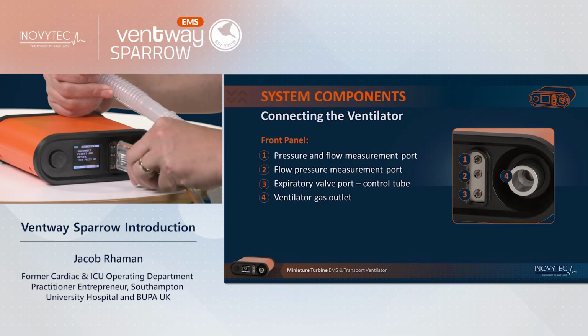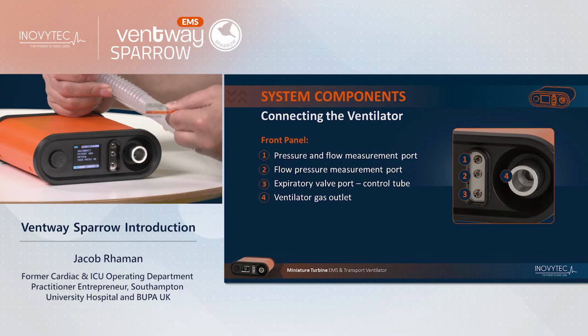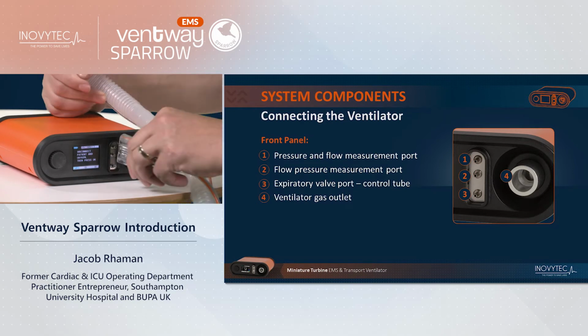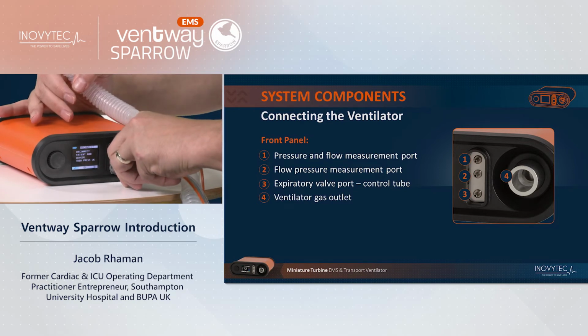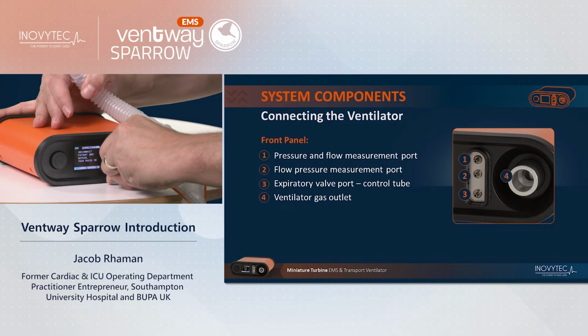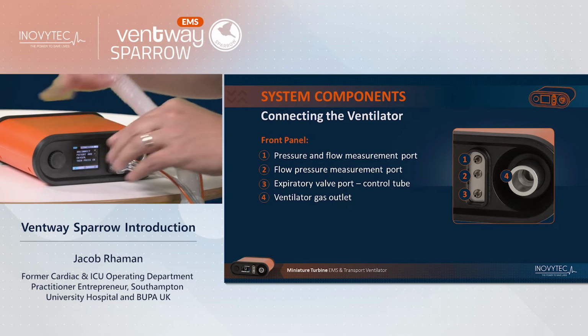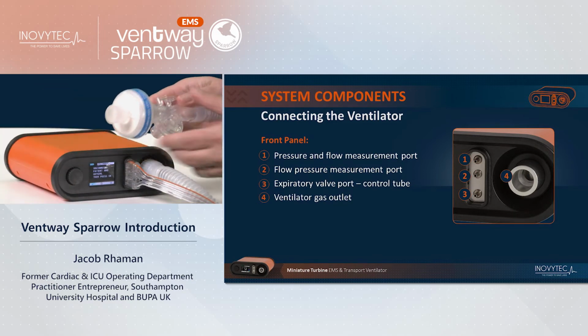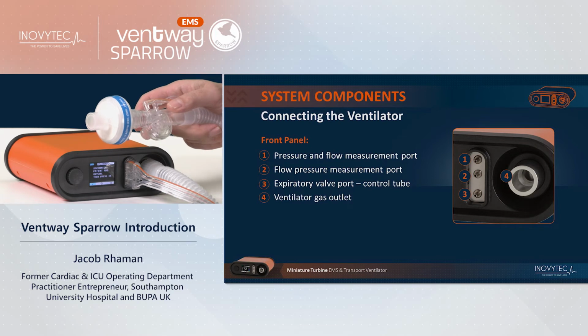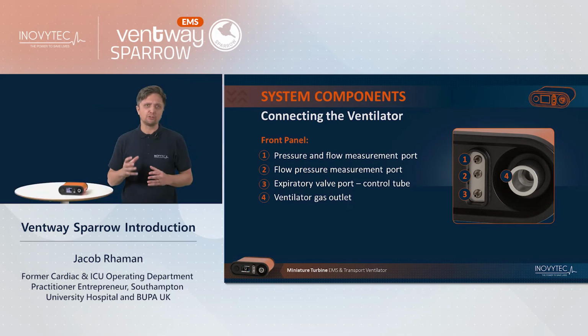On the patient circuit, the end which is connected to the Ventway Sparrow can only be connected in one way, assuring that the sensor tubing orange line is facing upwards. At the end of the patient circuit, a HME filter must be added before attaching to the patient airway adjunct. Endotracheal tube, supraglottic airways, for instance, can be used, as well as a face mask for ventilation.